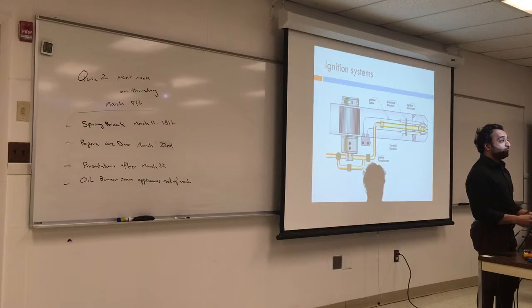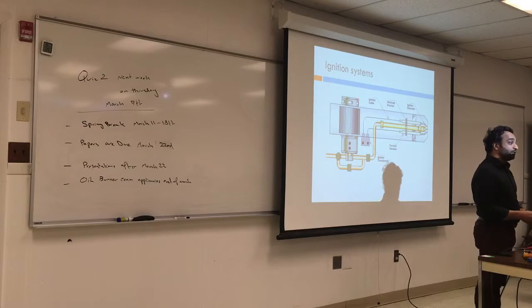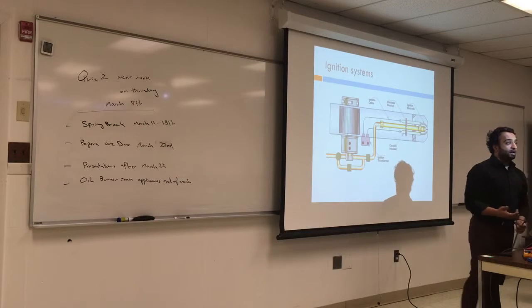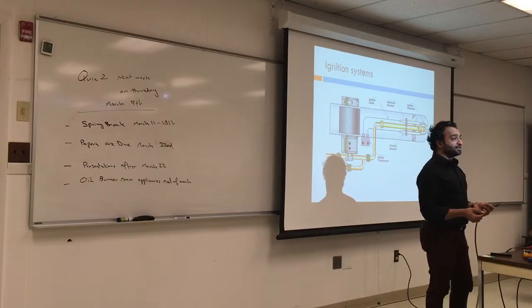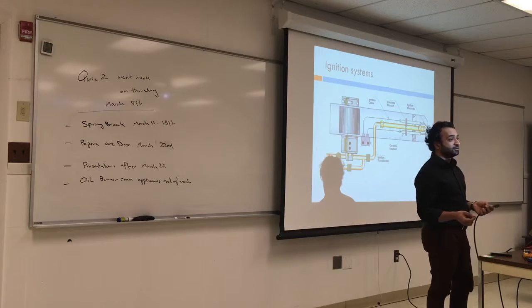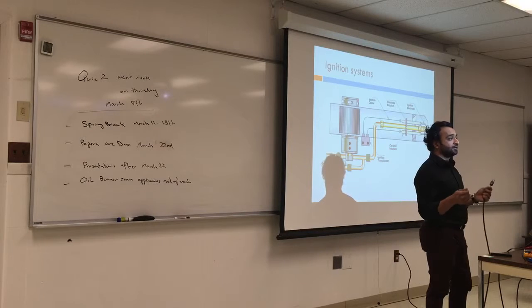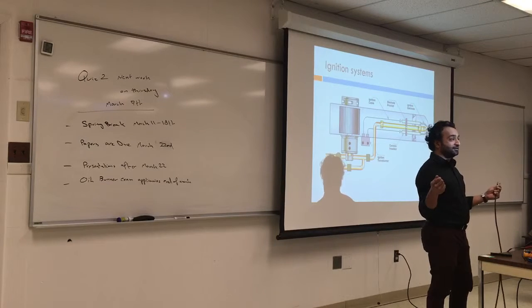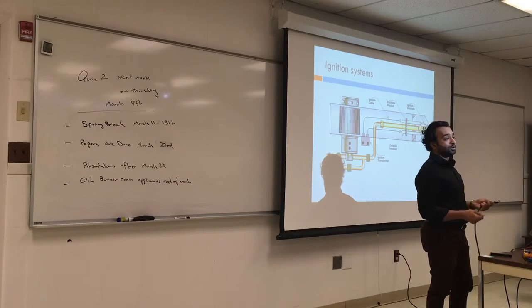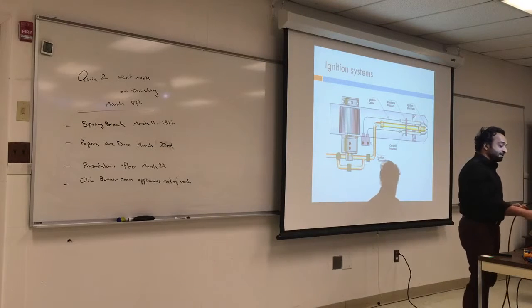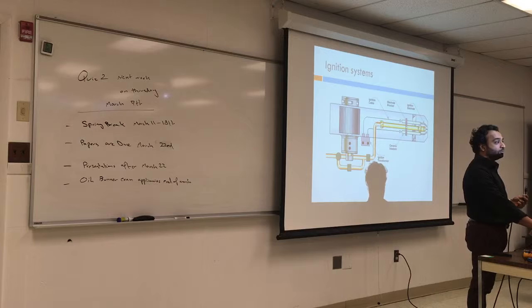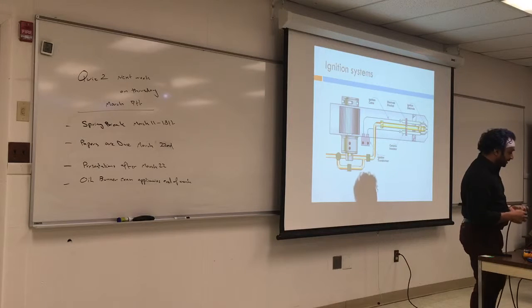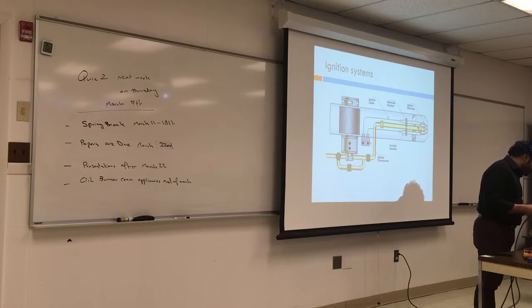I had some students who wired both of them to hot. What would that do? It's going to burn. You'll see smoke. Why? If you put both in hot, how much voltage are you getting into the transformer? Hot and hot, how much power is in hot? 110. So if you get 110 and 110, that's 220. You're going to fry your igniter. Same thing for older motors. Probably they will come in two colors, and back then they just expected everybody to know that there has to be a neutral. So now they're trying to make it more user-friendly, I guess.